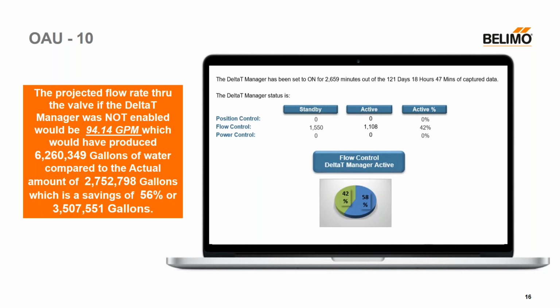So eliminating that waste is eliminating over pumping for the system and eliminating overflows and those thermal inefficiency surcharges. One thing to mention here too is the pump affinity law, which we ran into a bunch for them. Pump affinity law just states that a change in flow can be a cubed effect on our pump. Moreover, if we know our delta T was 14, like it's designed for this example, and they were achieving 7, or half of 14, that's twice the flow and 8 times the pump horsepower. So a dramatic effect, and that really shows why this was such a big deal to them.